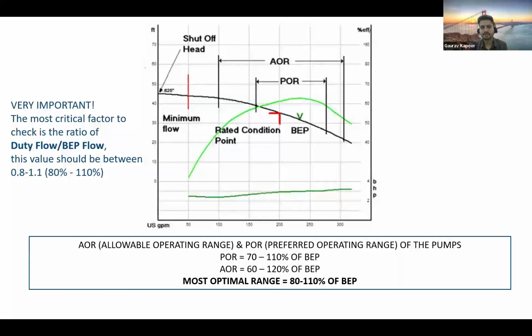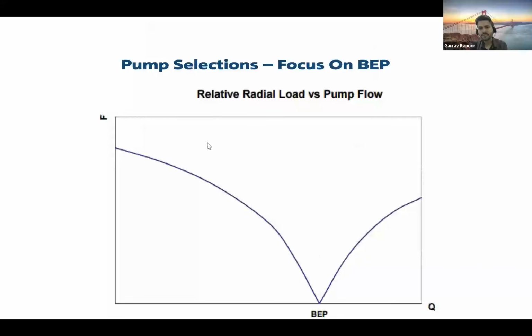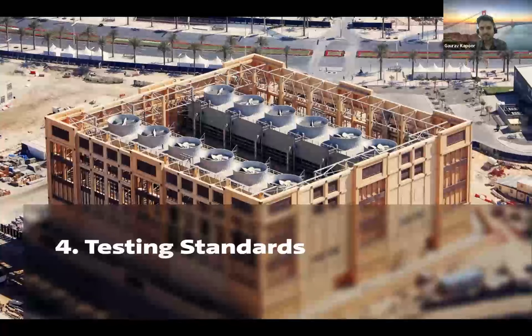and there you can have this particular range of 90 to 110%. Now this is the reason: at the best efficiency point, your relative load, as you can see, is 0, and as you move far away from the BEP point, your radial forces increase drastically, which is not recommended. Now quickly looking into the testing standards.